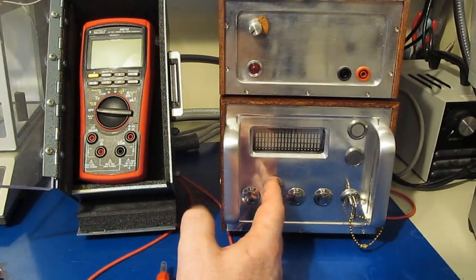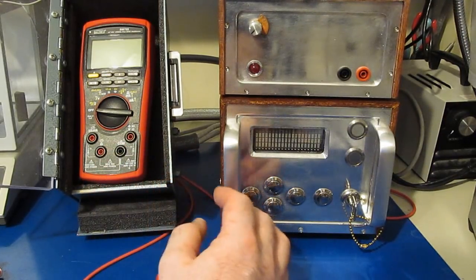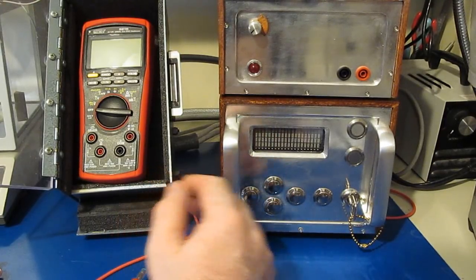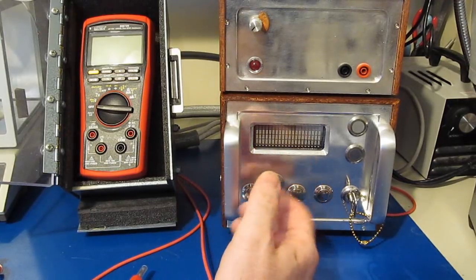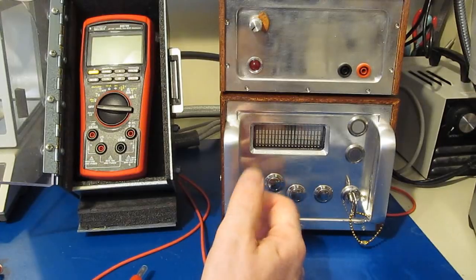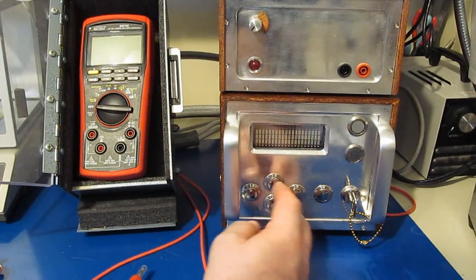Again, what I'm interested in is how robust these meters are electrically. It's a big difference between those tests. When I started out, I looked at what the industry was doing for testing the meters. Of course, they have the IEC 61326 EMC standard, and that covers the static discharge test that we just ran. Basically, I was looking for something that more closely mimicked what I was doing in the lab.